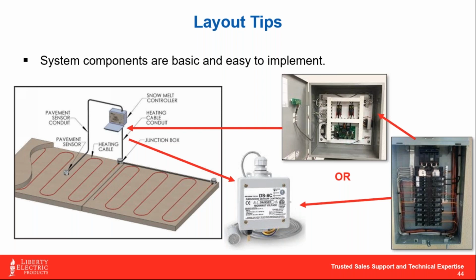Working it from left back to right, you might have a pavement sensor and an aerial sensor out there looking for temperature and moisture. If it recognizes it, it sends a signal back to that controller. That controller sends its signal back to the contactor relay panel, which closes contacts, allows power to pass to the heating cables, and away you go.